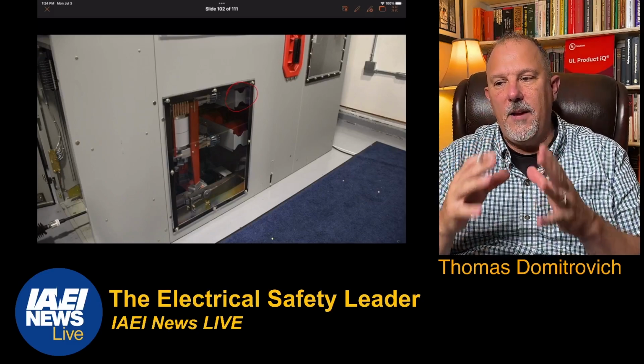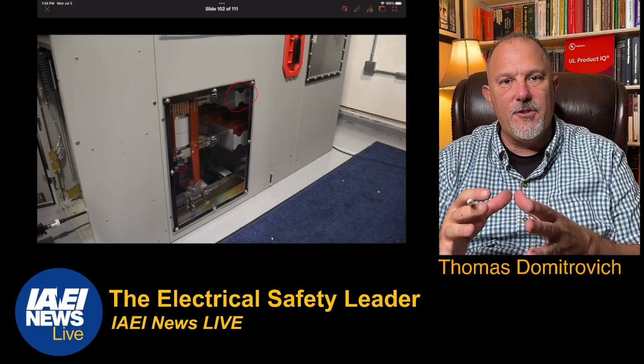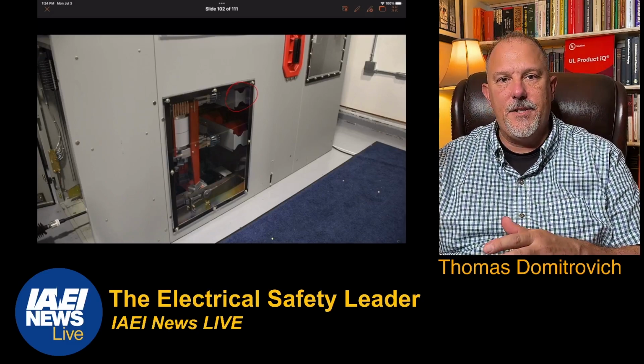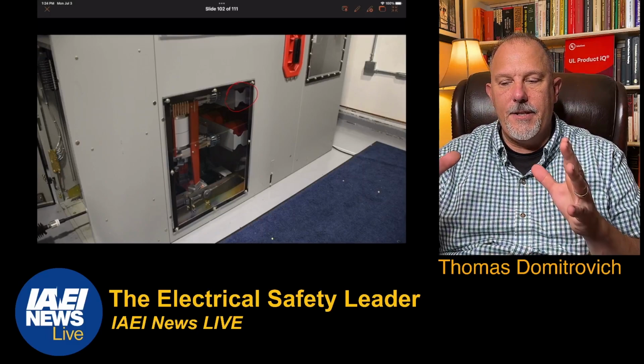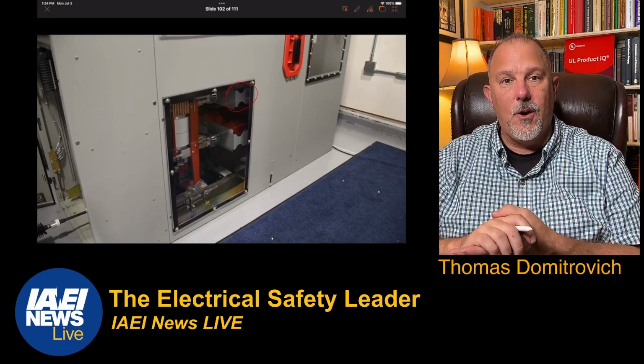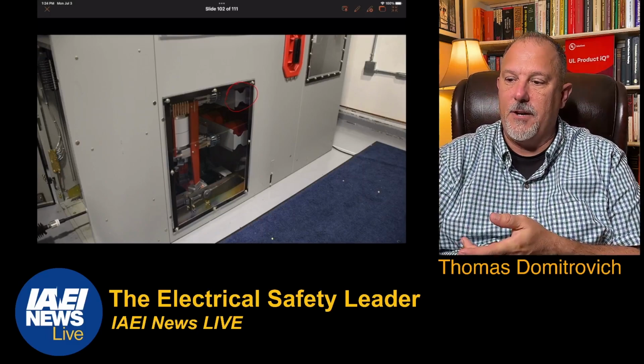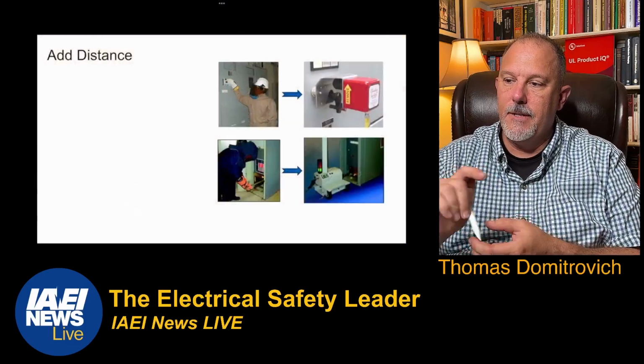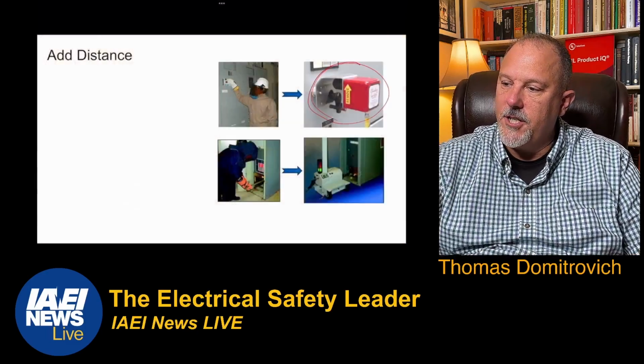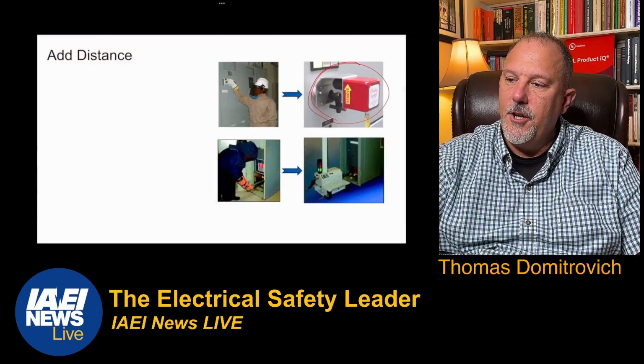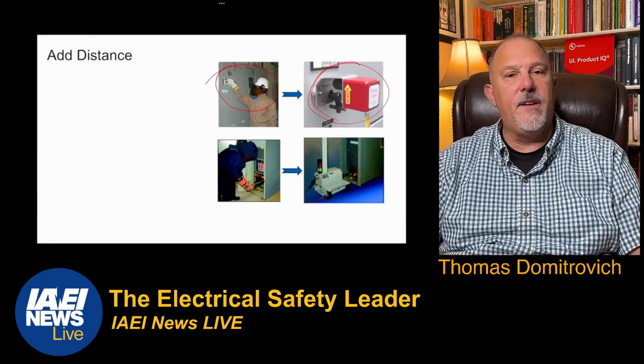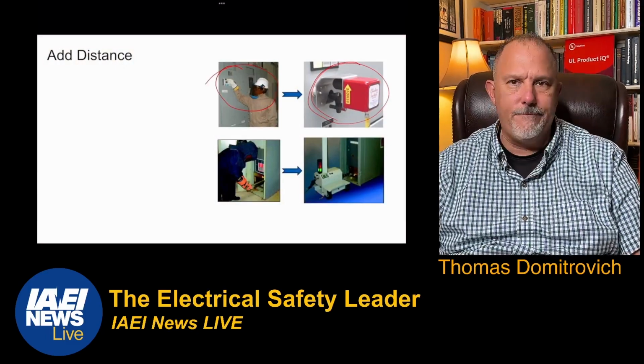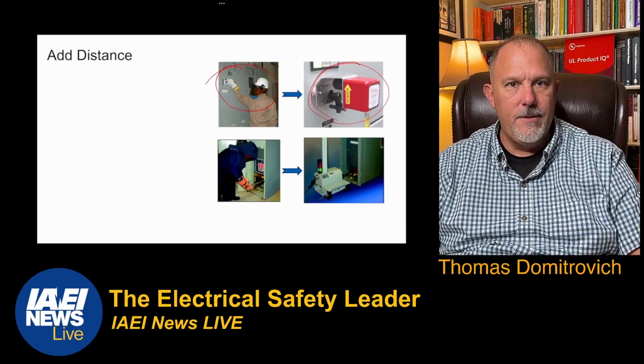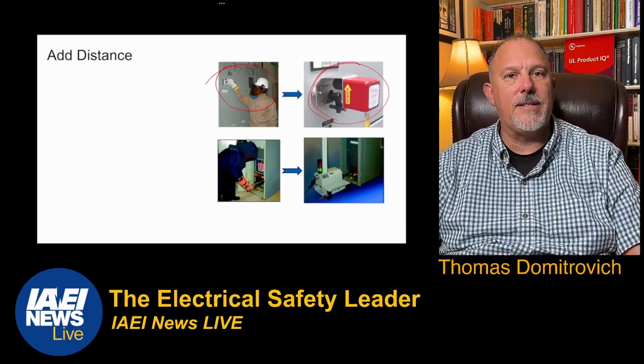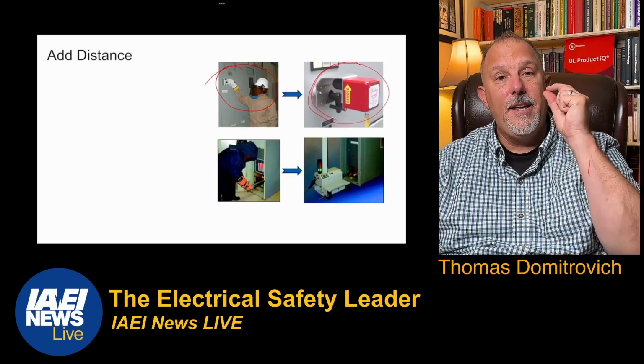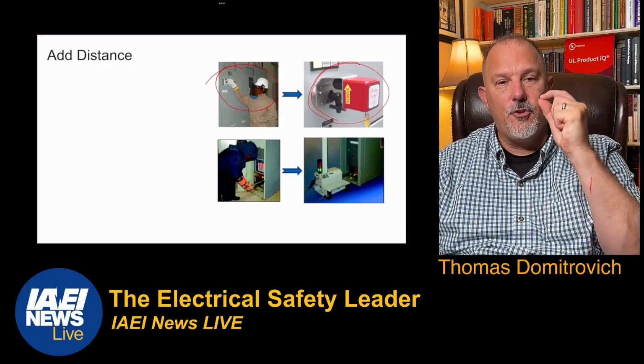So now you're able to rack that medium voltage breaker out from a distance, and all of that occurs while you are well outside of the arc flash boundary. So this is what they call a chicken switch. That's another solution. You want to avoid being in front of the equipment. I don't care what condition the equipment is in. Anytime you can get an electrical worker outside of that zone, here's what happens. You create a habit.